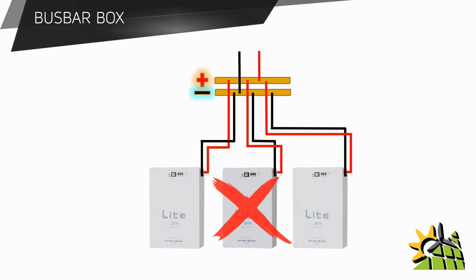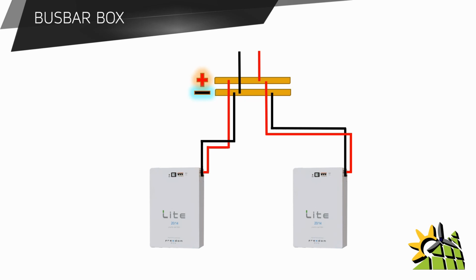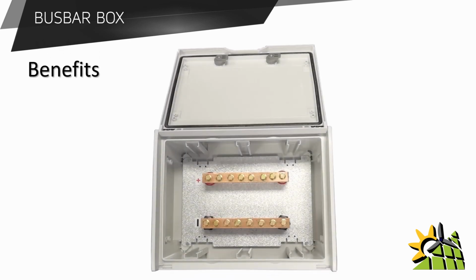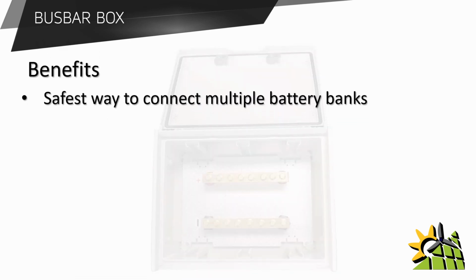Now if one battery were to be damaged, the other two batteries will still continue to perform as it was designed for. And to remove that one battery to be repaired, you don't have to change any cables. You simply have to remove the cables from the busbar box, and the other batteries will still continue to perform as designed. So the benefits of the battery busbar box is, first, it provides a safe way to connect multiple battery banks together.